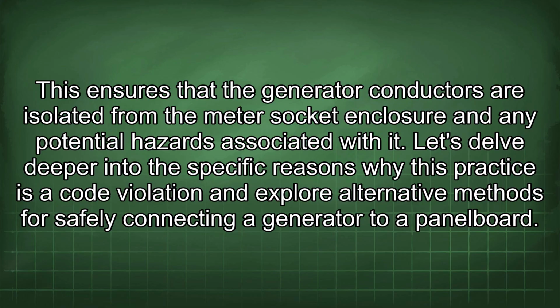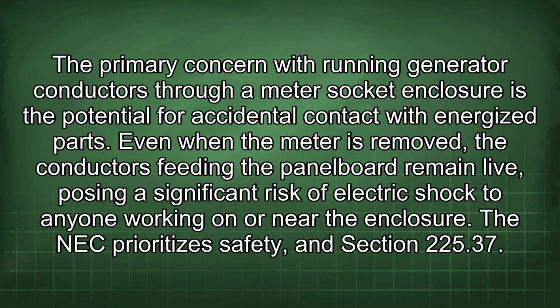Let's delve deeper into the specific reasons why this practice is a code violation and explore alternative methods for safely connecting a generator to a panel board. The primary concern with running generator conductors through a meter socket enclosure is the potential for accidental contact with energized parts. Even when the meter is removed, the conductors feeding the panel board remain live, posing a significant risk of electric shock to anyone working on or near the enclosure.